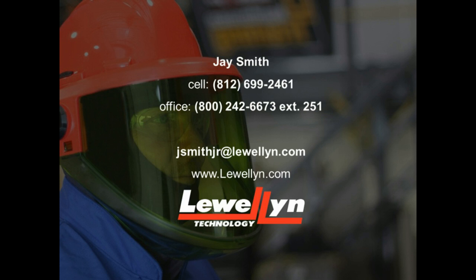So the category method works in that respect. We've seen other folks who've created their own site-specific PPE categories. You're allowed to do that, as long as you're dressed for the calorie rating on the equipment. If you want to call it CAT 27 in your program, you can, as long as that means something to someone, they're trained on it, and it's documented in your policy. But the label and the clothing itself must have the calorie rating on it. Behind the scenes, you can designate it however you like.